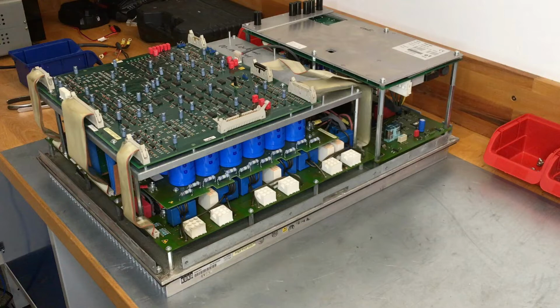Okay, let me explain. In principle, the PM6600 is a frequency converter, or to be more precise, 6 frequency converters for the respective motors, which means that the 3 phases of a 400 volt 3-phase supply are rectified to a common DC link voltage of up to 600 volts. And from this DC voltage, a low-frequency 3-phase supply is then produced for the individual motors with the help of pulse width modulated signals. The great thing about the PM6600 is that it's very modular.